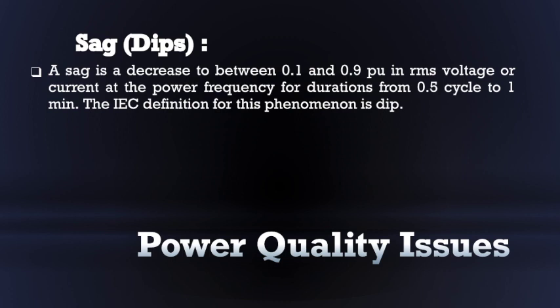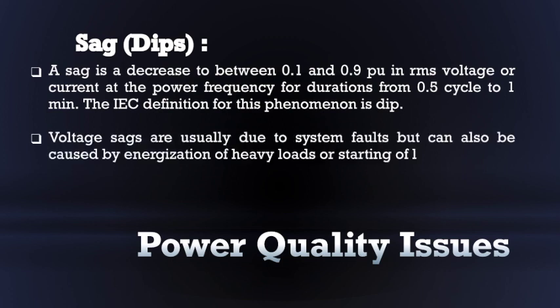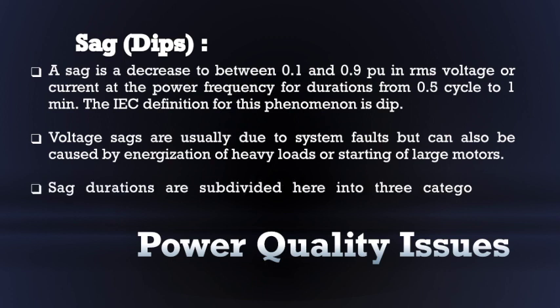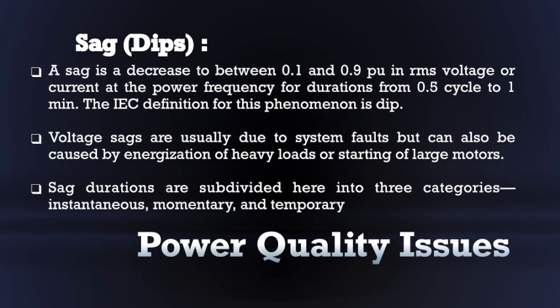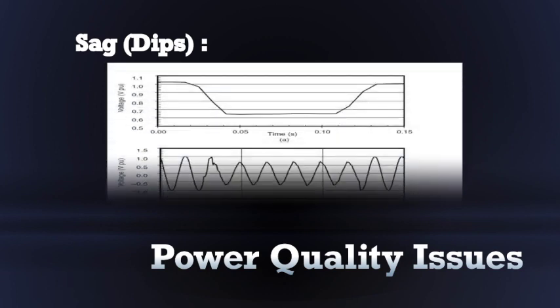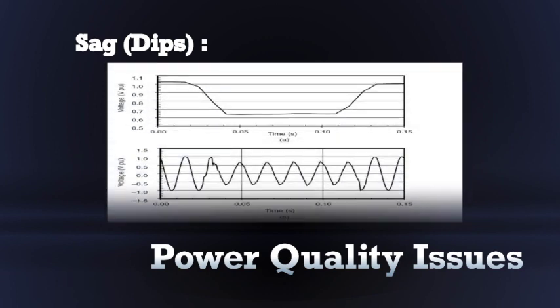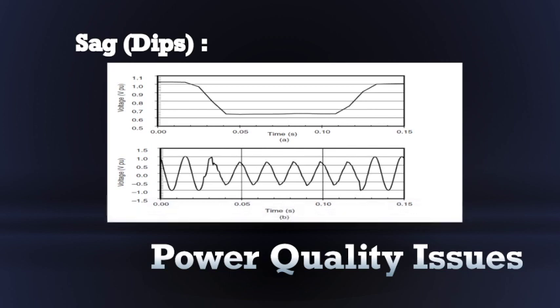The IEC definition for this phenomenon is dip. Voltage sags are usually due to system faults but can also be caused by energization of heavy loads or starting of large motors. Sag durations are subdivided into three categories: instantaneous, momentary, and temporary. You can see the figure. The figure shows a typical voltage sag that can be associated with a single line to ground fault on another feeder from the same substation. In the figure, you can see a reduction in the voltage, which indicates sag.